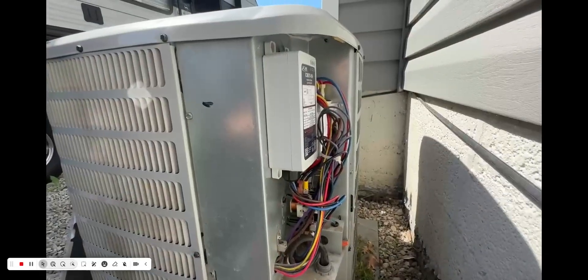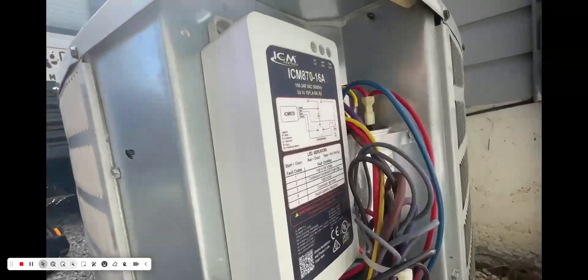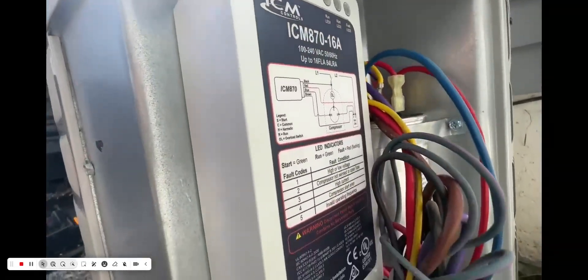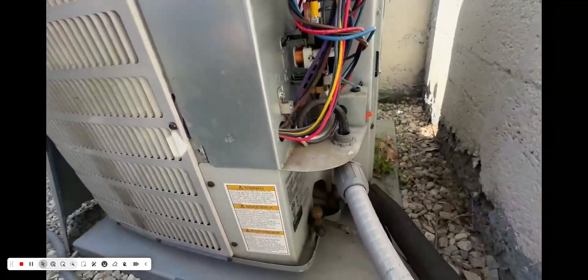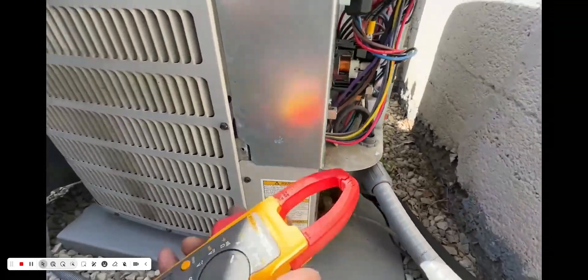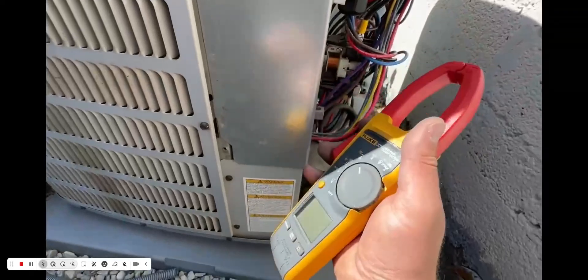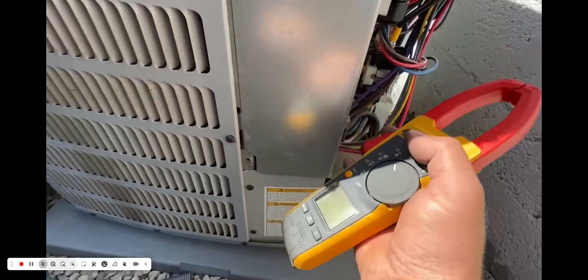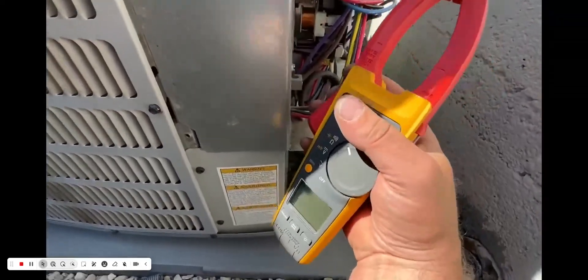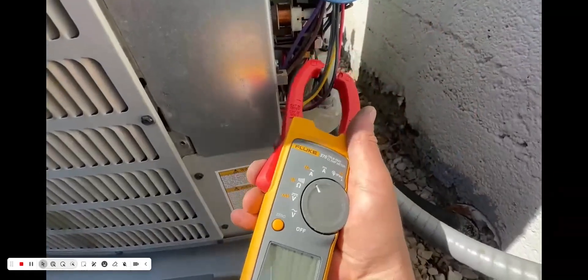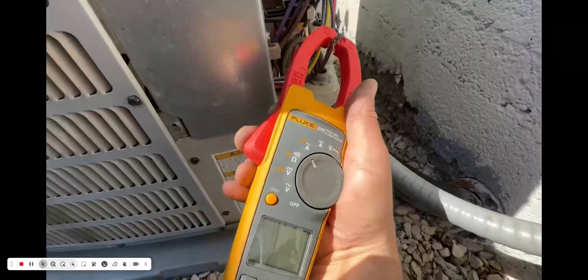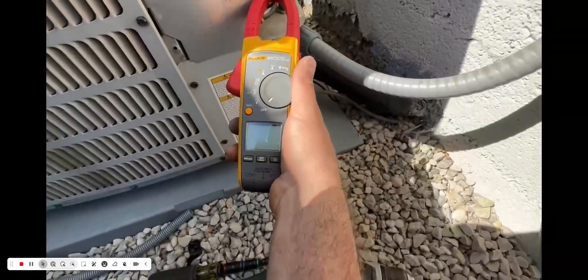Okay, so we got all four wires hooked up on our ICM 870, so we are ready to rock and roll. Now I'm going to hook this up to the same exact common wire here that comes off our compressor, and let's see what the inrush amps are for this guy.